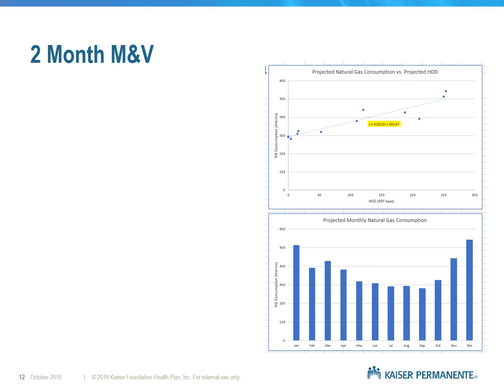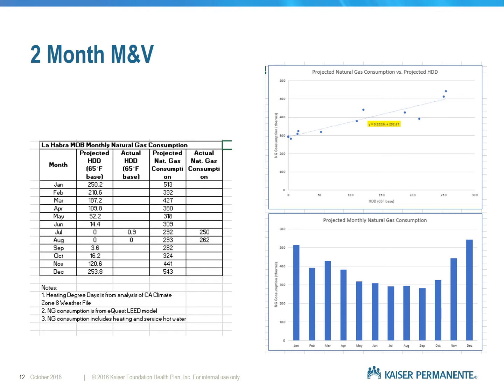Well, then when your monthly data comes out, you can compare it to that model. And if it's within about 10% of the model, great. If it's more, then something isn't working to the design intent, and it's time to go fix it. In this case, so far, the building is running at or below the model. We'll see if that continues as we get into the heating season.